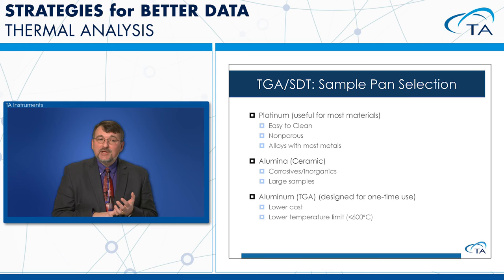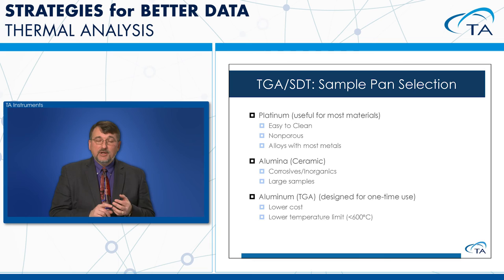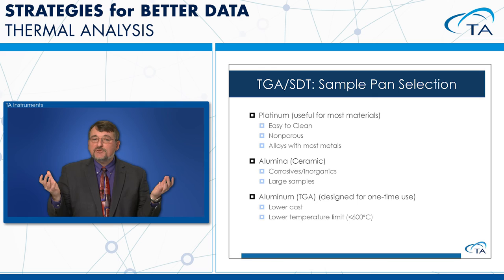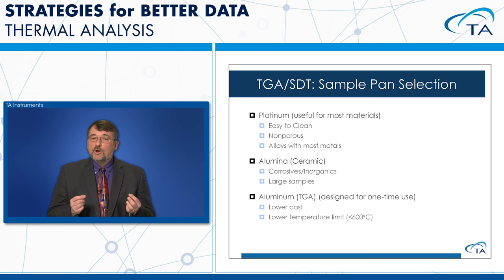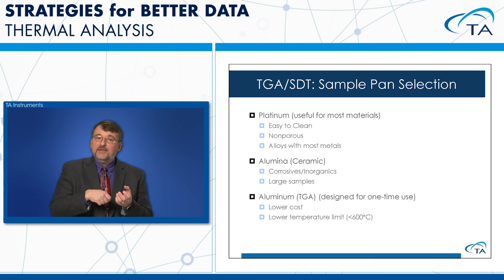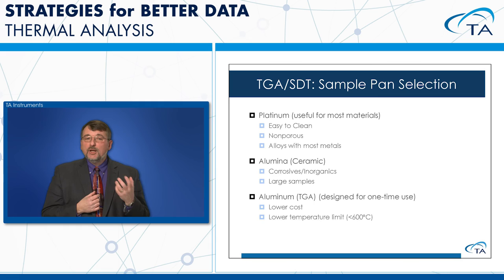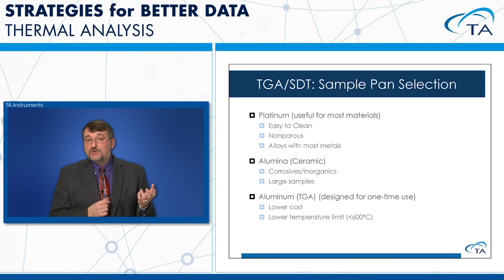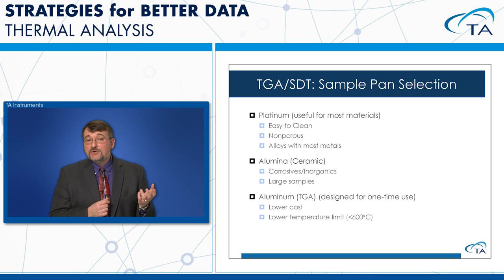Pan material matters: platinum pans are easy to clean by burning off the sample and are non-porous, but can alloy with most metals. Alumina or ceramic pans are good for corrosive and inorganic samples and larger samples, though slightly harder to clean due to porosity. Aluminum pans are essentially single-use — you can clean them in solvent, but heating to burn off the sample melts the aluminum.